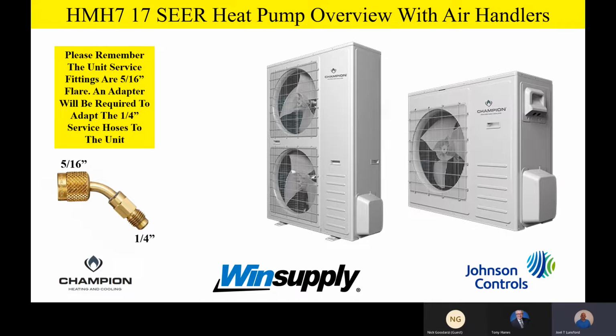Now, one thing I always like to mention whenever we do this training, on top of everything else, is the fact that these units are not mini splits. Now, they look like mini splits. They have a similar cabinet look, and they even have similar technology as far as the compressor modulating from 35 to 100% capacity. So we have some modulating capability on the outdoor unit, even though it's very, very simple to wire up and it's designed to hook up to just a standard air handler with a standard expansion valve on the indoor coil. So I just want to stress that one more time.